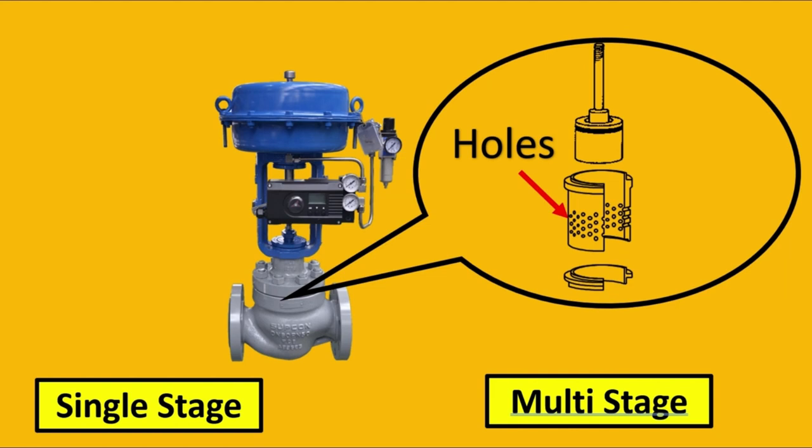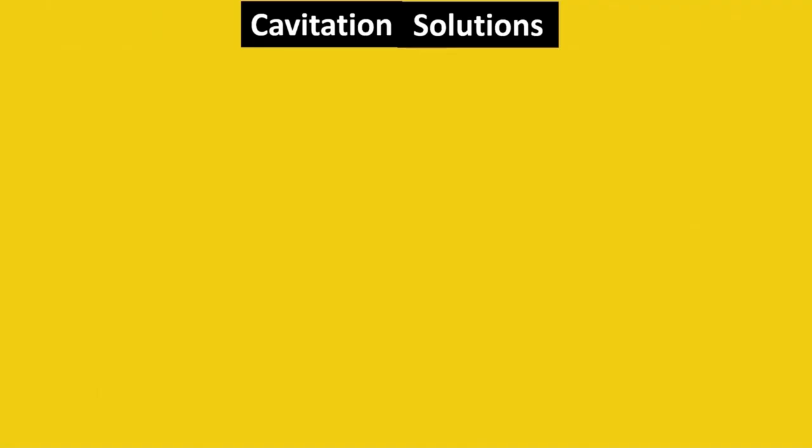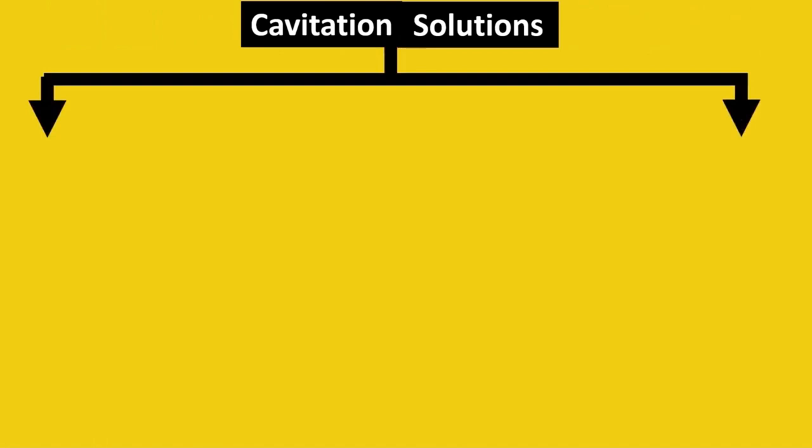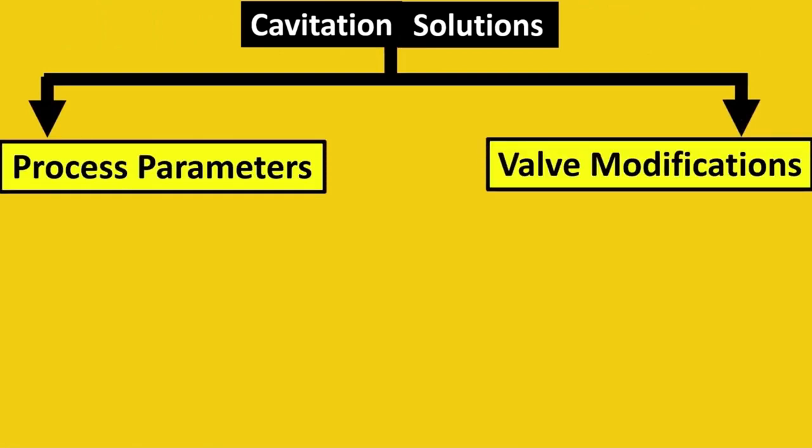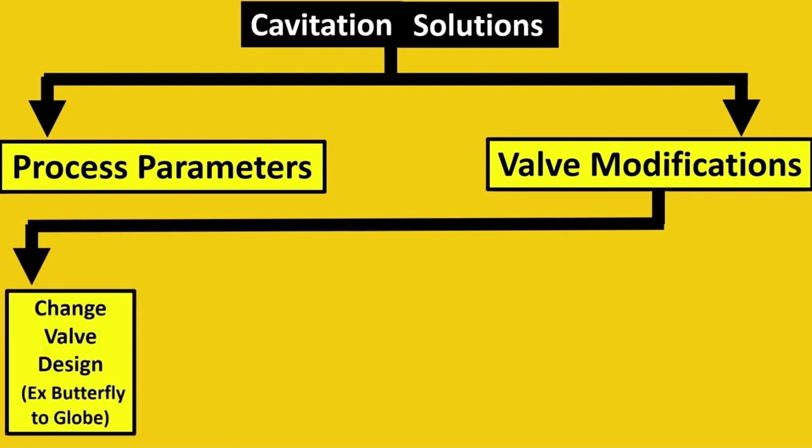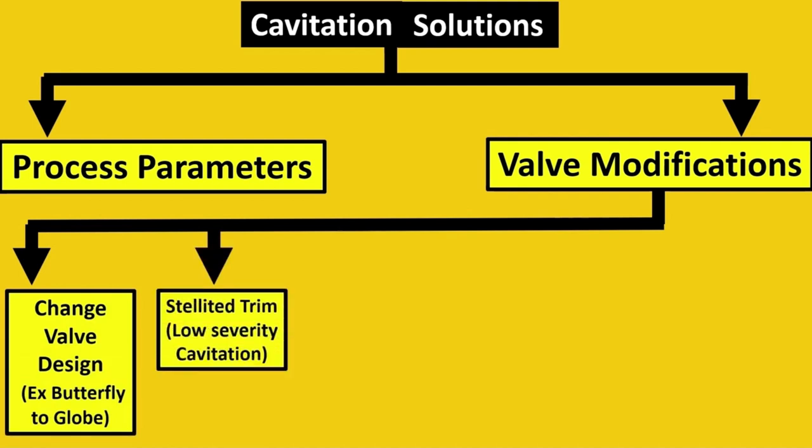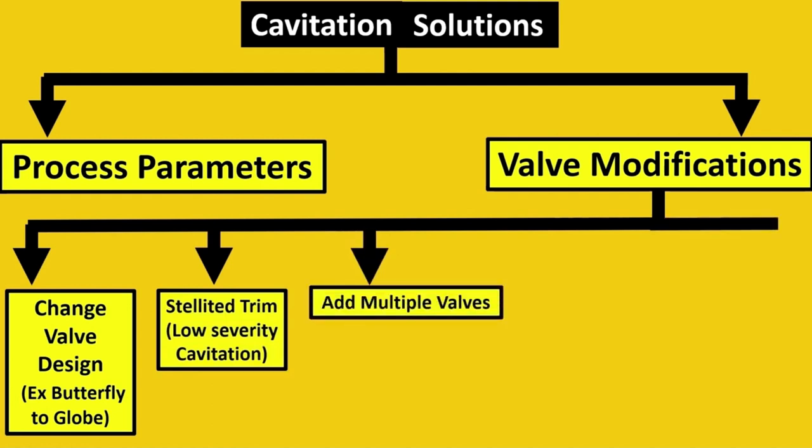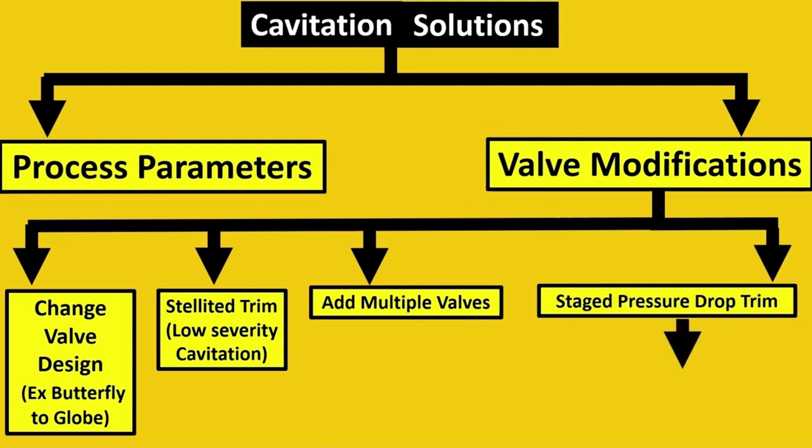For cavitation solutions, there are process parameters and valve modifications. For valve modifications: first is changing valve design - butterfly has one pressure drop point, but globe has multiple, so globe is better. Second is stellited trim, where you harden the trim material for low severity cavitation so it can sustain damage longer. If that's not working, go for multiple valves, or if that's an issue, go for staged pressure drop trim which can be single-stage or multi-stage.